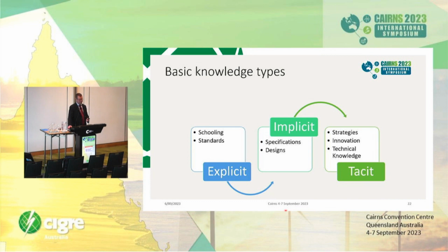So maybe a couple of examples of what that means. Explicit would be, say, a document stating the phase-to-phase clearance for a 220 kV substation is 2.3 meters. The implicit is using that 2.3 meters when you're designing your substation and producing drawings and specifications. Taking that to a tacit level is when you've absorbed that - you understand fully why it's 2.3 meters. You know it's because of the insulation levels of your system, to ensure you don't get flashovers, and that it's relative to the lightning impulse level and switching impulse level of your installation.